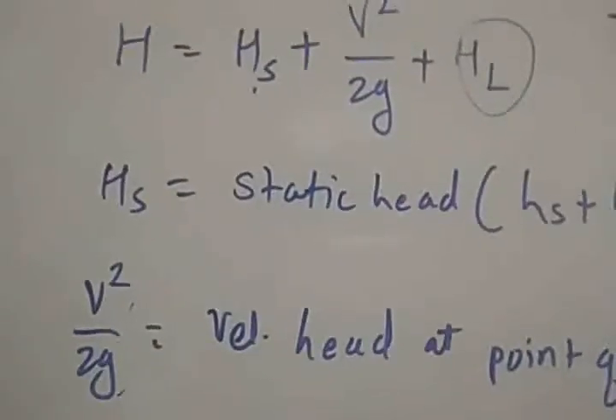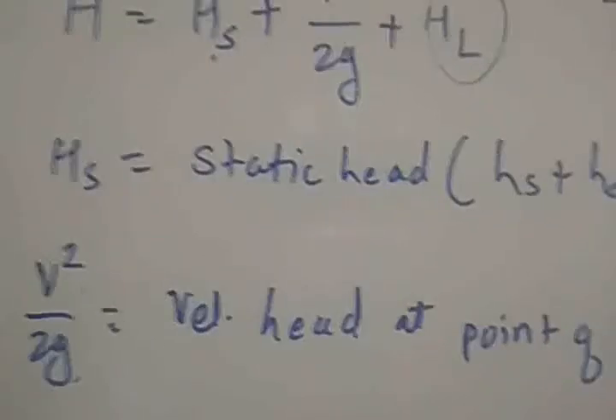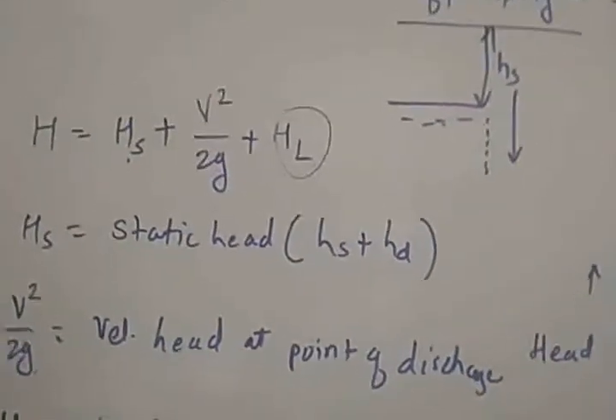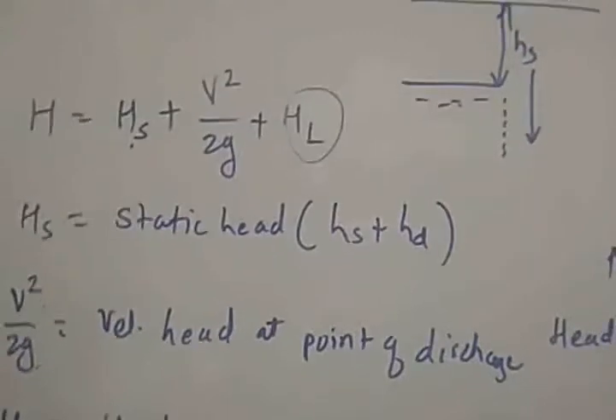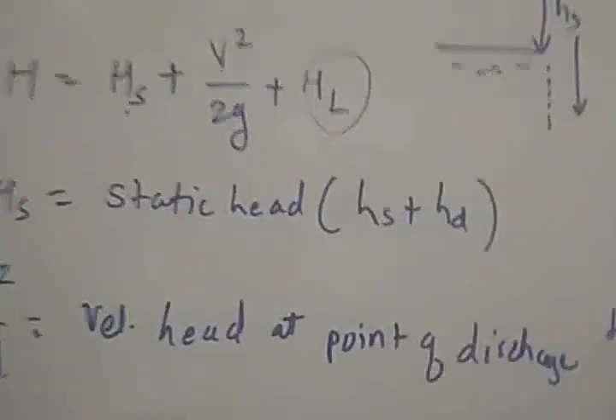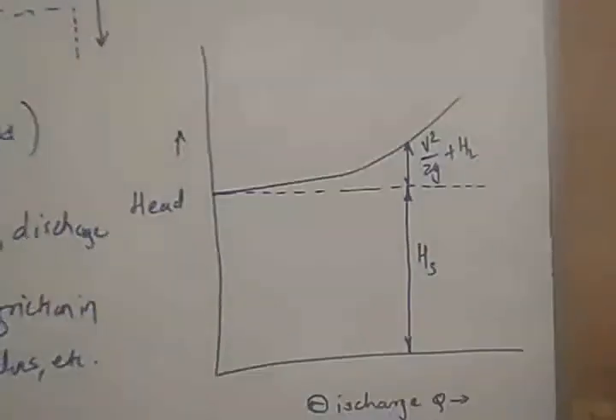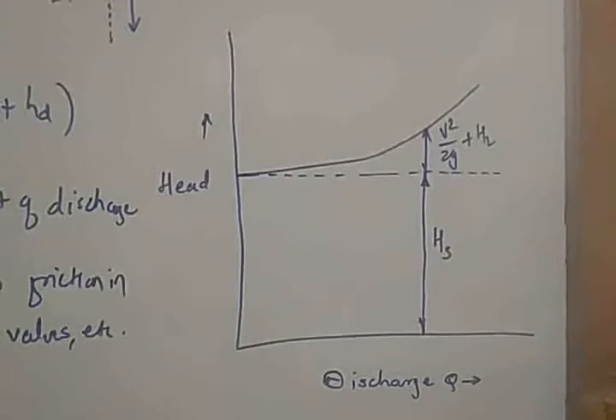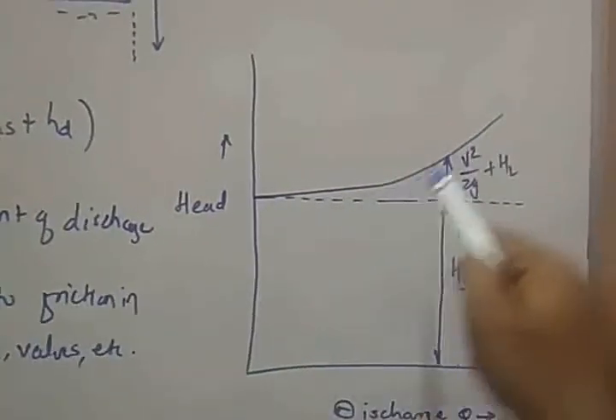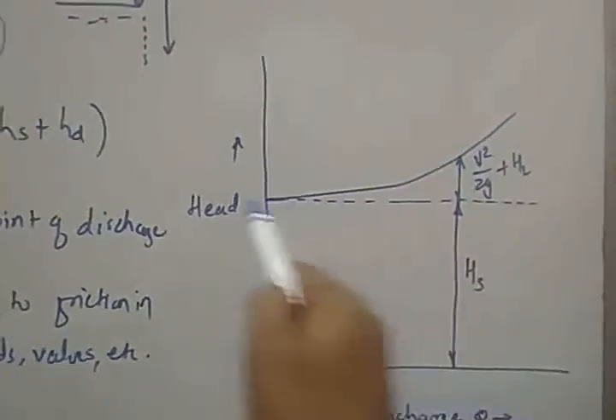Thus, the total head varies with varying flow rate and discharge. Either the flow rate will change or the discharge will change, the total head will vary. Hence, the plot of total head of pumping versus flow rate is known as the system head curve, which I have drawn over here. The plot of total head versus discharge is known as the system head curve.